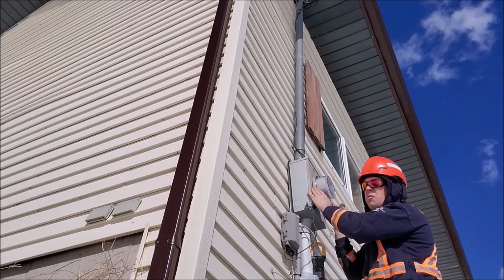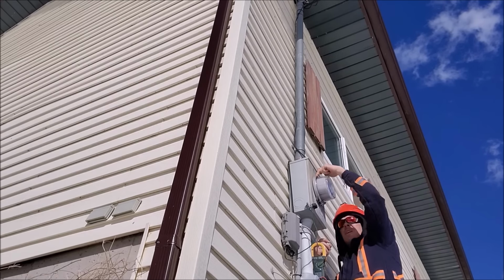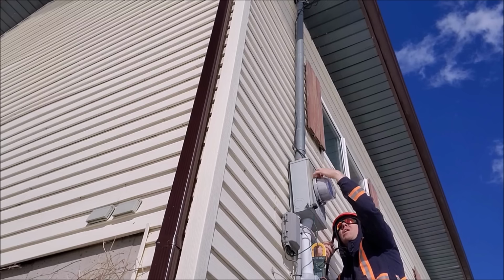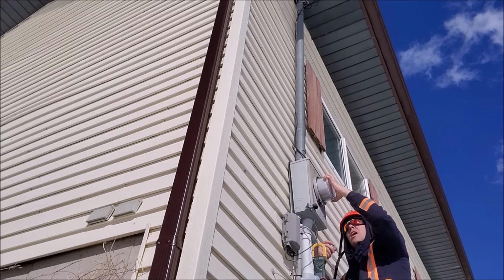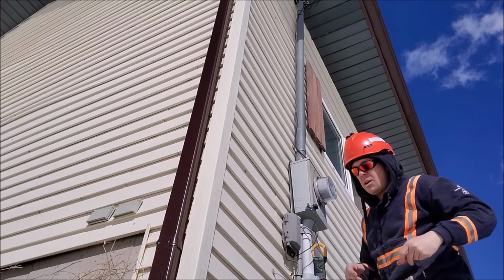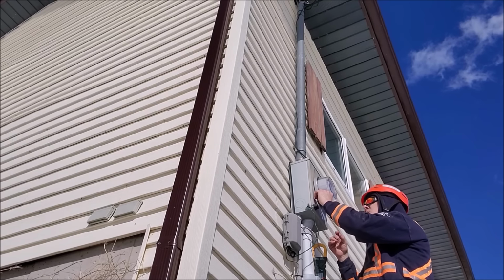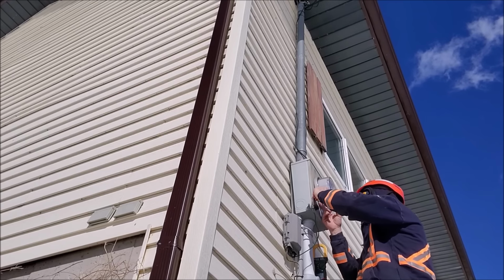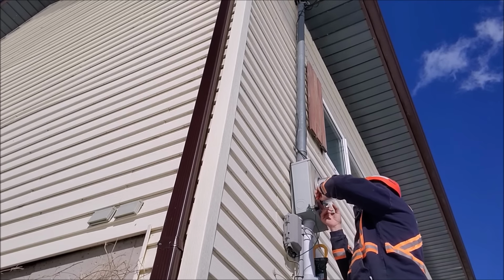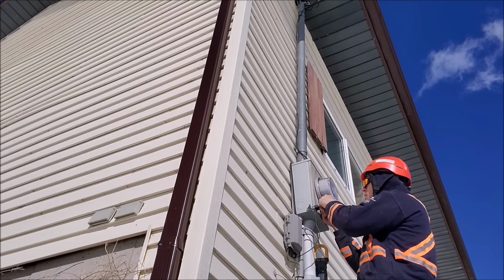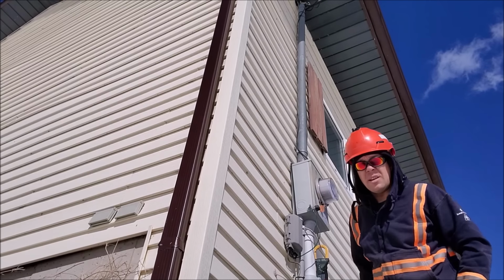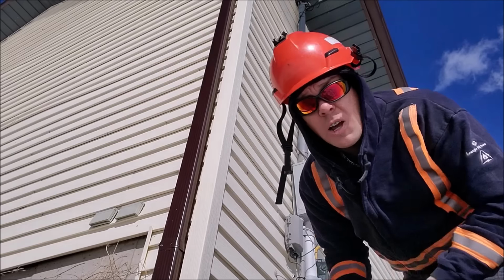Now, when installing these meter rings, you'll want to make sure the ring grabs the steel in behind the meter as well as the case of the meter. Otherwise, you're defeating the purpose of having the meter ring. So you're going to seal it. And that's it. Let's go talk to the customer, let them know what we found.